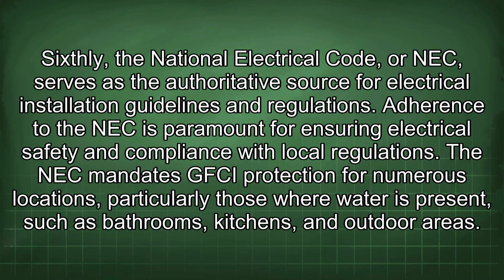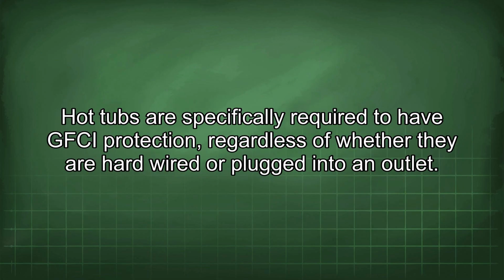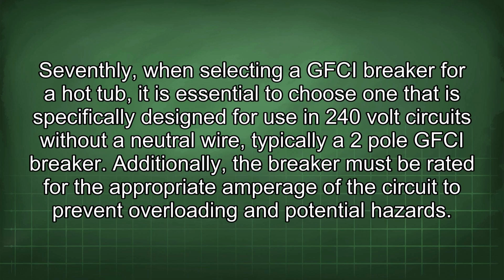The NEC mandates GFCI protection for numerous locations, particularly those where water is present, such as bathrooms, kitchens, and outdoor areas. Hot tubs are specifically required to have GFCI protection, regardless of whether they are hardwired or plugged into an outlet. Seventhly, when selecting a GFCI breaker for a hot tub, it is essential to choose one that is specifically designed for use in 240-volt circuits without a neutral wire, typically a 2-pole GFCI breaker. Additionally, the breaker must be rated for the appropriate amperage of the circuit to prevent overloading and potential hazards.